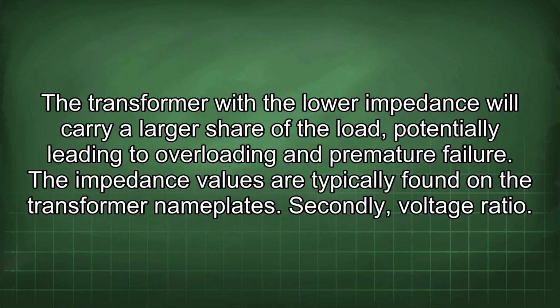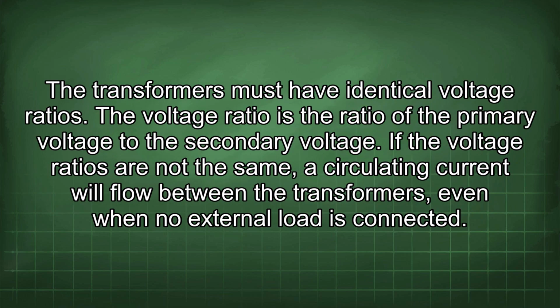The transformer with a lower impedance will carry a larger share of the load, potentially leading to overloading and premature failure. The impedance values are typically found in the transformer nameplates. Secondly, voltage ratio. The transformers must have identical voltage ratios. The voltage ratio is the ratio of the primary voltage to the secondary voltage.